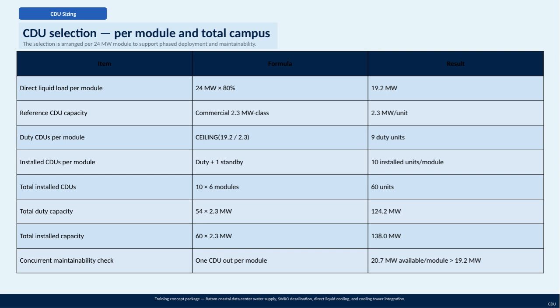In terms of capacity, the total duty capacity across 54 units is 124.2 megawatts, while the full installed capacity, including the standby units, sums up to 138 megawatts. An important check is concurrent maintainability. Even if one CDU is taken offline per module for maintenance, the remaining capacity of 20.7 megawatts exceeds the required 19.2 megawatts, ensuring continuous operation without thermal performance compromise. This approach, combined with the training concept package covering water supply, desalination, direct liquid cooling, and cooling tower integration, ensures a robust and maintainable cooling infrastructure for the data center.